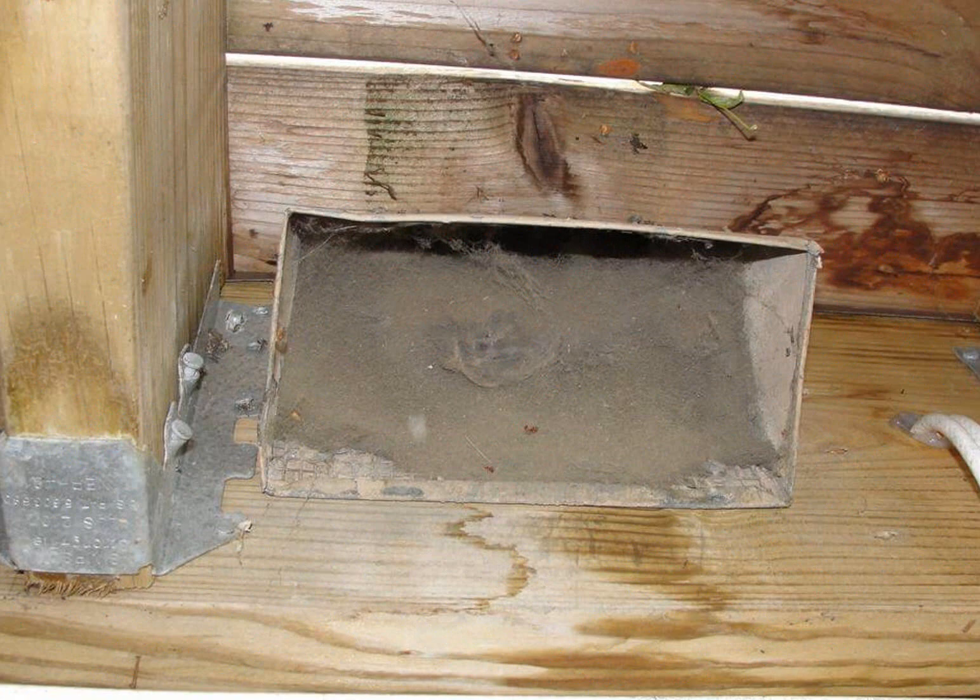That's a good takeaway. When it's not properly maintained, however — and most of them aren't — you're probably going to have a clogged intake. The intake at the exterior of the home gets all clogged up with cottonwood, mosquitoes, and other debris. No air comes in, it gets blocked. So if no air is coming in but air is still exhausting, that puts the home under negative pressure — the house is looking for more air to replace what's leaving. Where does it get that air? Through cracks in the foundation, openings around the sump basket that aren't properly sealed — it'll pull in soil gases, including radon. If you have a clogged intake, you've got the potential to actually increase radon levels during a short-term radon test. In that case, it'd be better for the HRV to not be running at all.